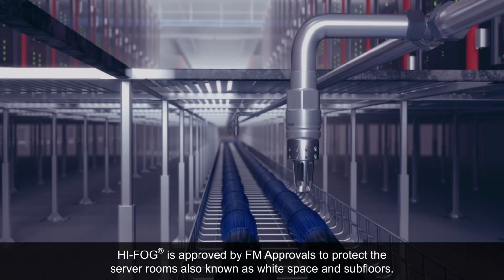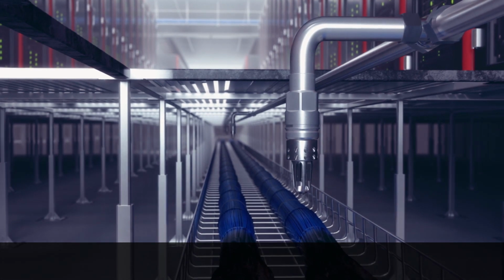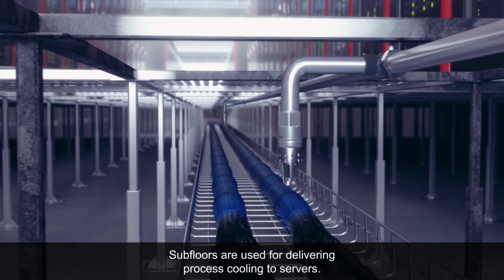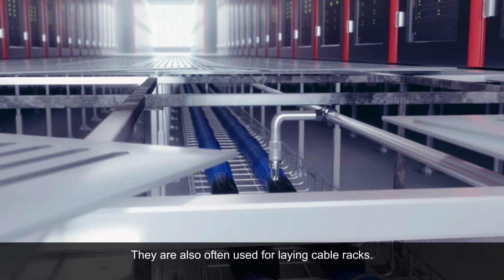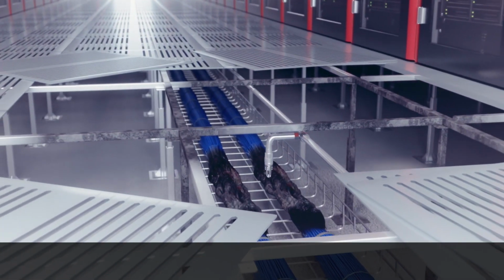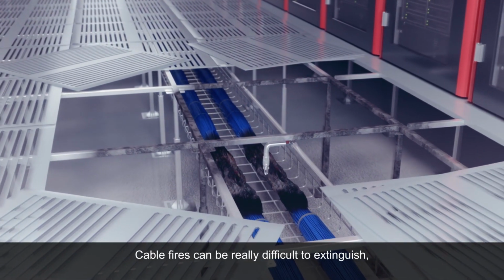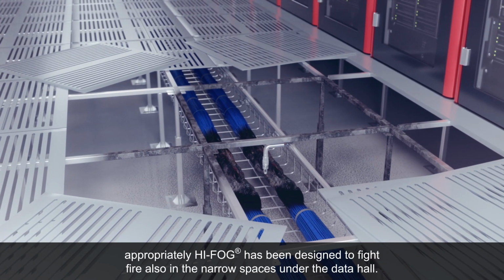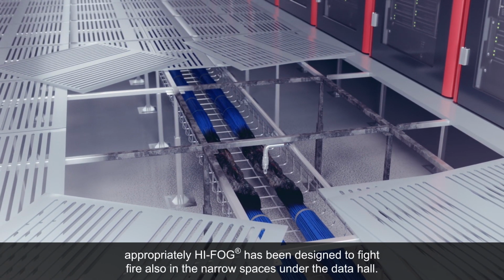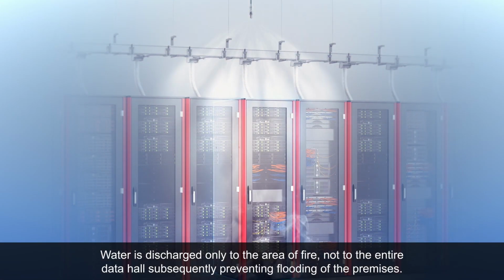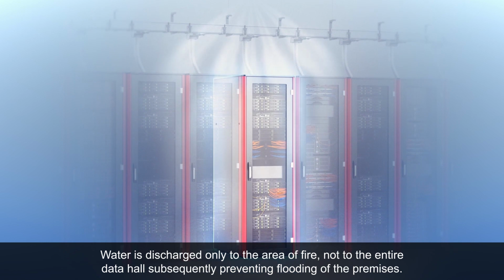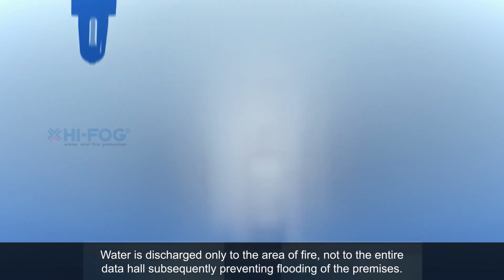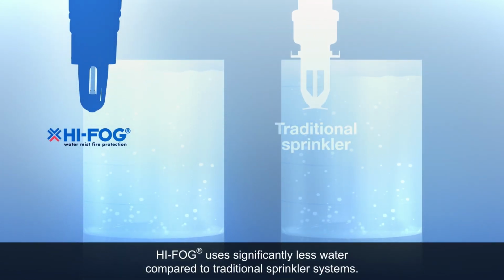HI-FOG is approved by FM Approvals to protect the server rooms, also known as white space, and subfloors. Subfloors are used for delivering process cooling to servers. They are also often used for laying cable racks. Cable fires can be really difficult to extinguish. Appropriately, HI-FOG has been designed to fight fire also in the narrow spaces under the data hall. Water is discharged only to the area of fire, not to the entire data hall, subsequently preventing flooding of the premises. HI-FOG uses significantly less water compared to traditional sprinkler systems.